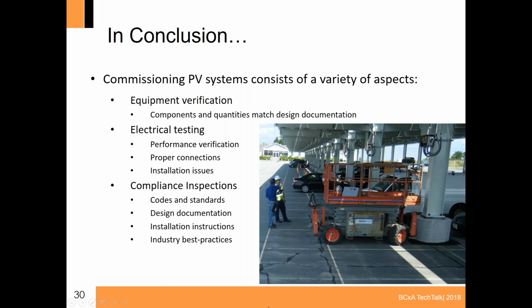So basically, in conclusion, commissioning PV systems consists of a variety of aspects. We have our equipment verification, where its components and quantities match the design documentation. So we're verifying that, yep, they installed what they said they would. Electrical testing, really that hands-on diving into it, verifying performance, verifying proper connections, helping identify installation issues.